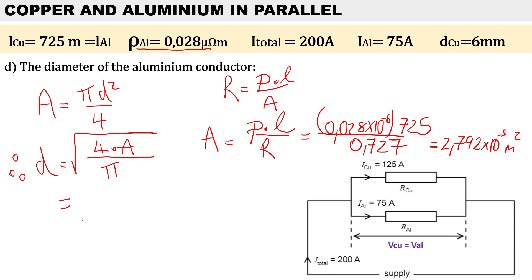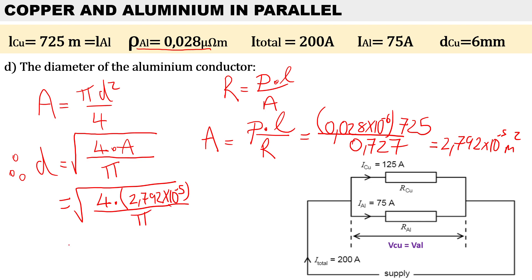Now we can work out the diameter. Don't forget the square root sign: diameter equals the square root of 4 times the area — 2.792 times 10 to the minus 5 meters squared — over pi. Therefore the diameter for the aluminium cable, simplified to millimeters, is 5.962 millimeters. Thanks for watching this video on two conductors in parallel.